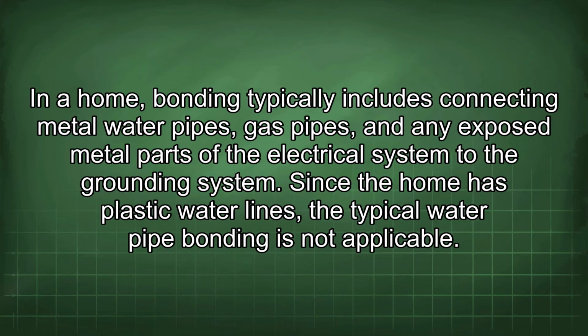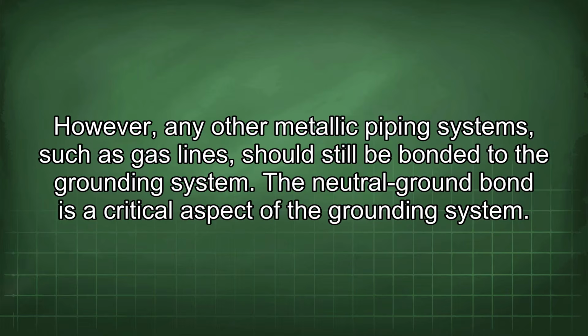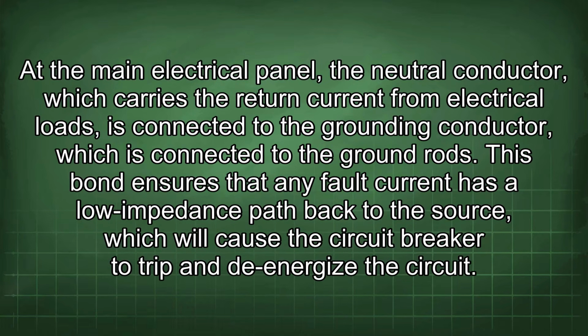Since the home has plastic water lines, the typical water pipe bonding is not applicable. However, any other metallic piping systems, such as gas lines, should still be bonded to the grounding system. The neutral ground bond is a critical aspect of the grounding system. At the main electrical panel, the neutral conductor, which carries the return current from electrical loads, is connected to the grounding conductor, which is connected to the ground rods. This bond ensures that any fault current has a low impedance path back to the source, which will cause the circuit breaker to trip and de-energize the circuit.